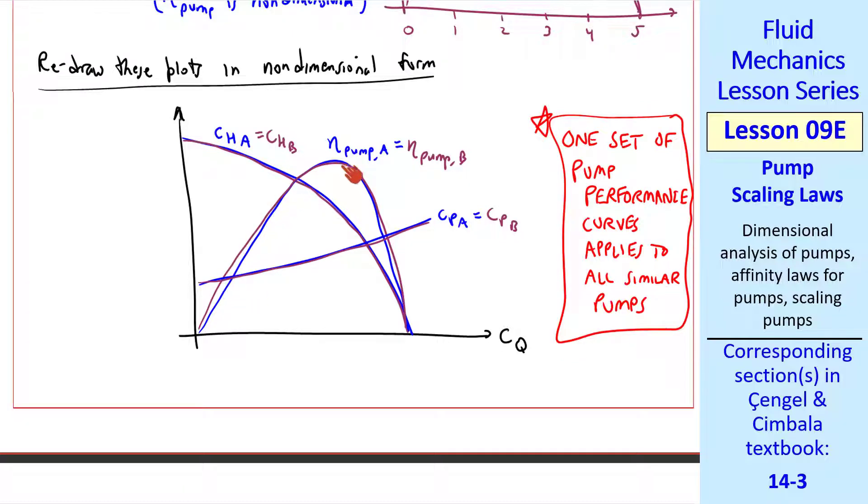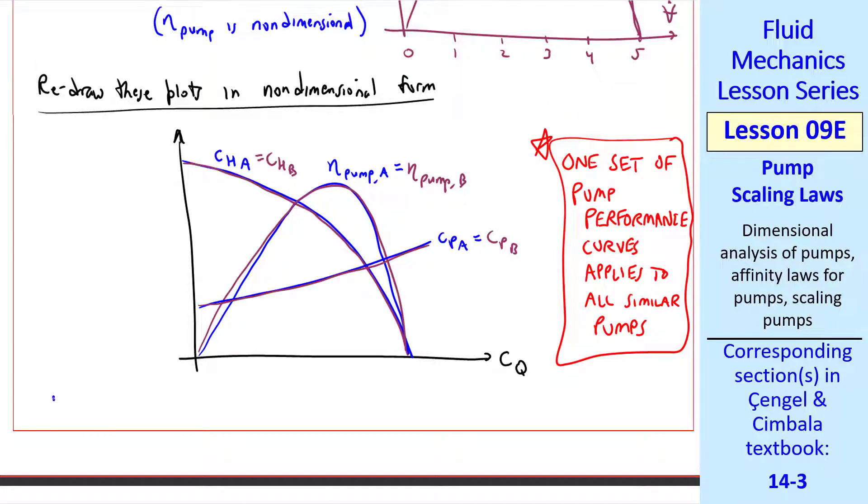So we can use this set of pump performance curves to scale our pump up or down. The caveats being that they must be geometrically similar and dynamically similar. For most problems, all this means is that the CQs match. And as mentioned before, we also have Reynolds number and roughness parameter which also need to be included at small Reynolds number, but we won't look at cases like that.